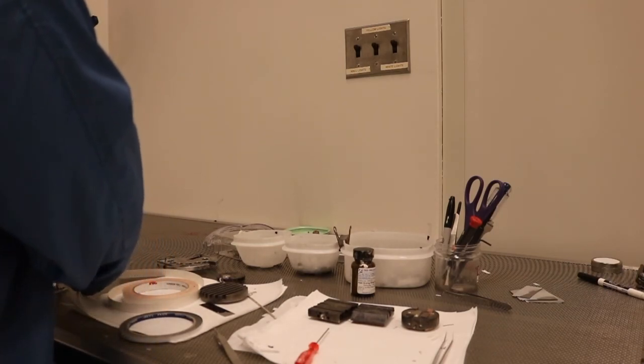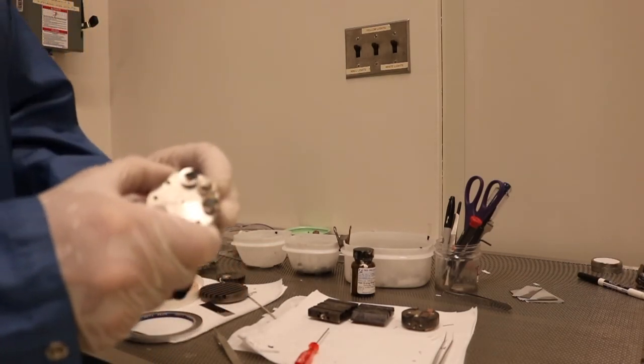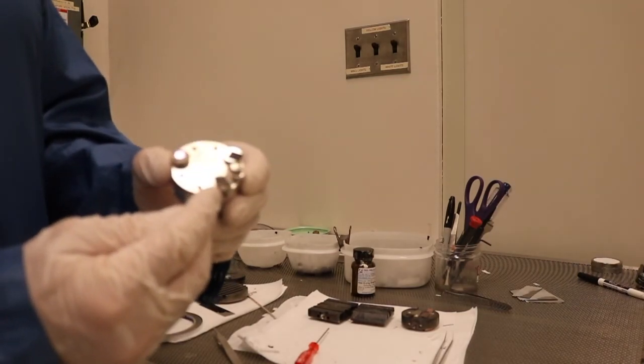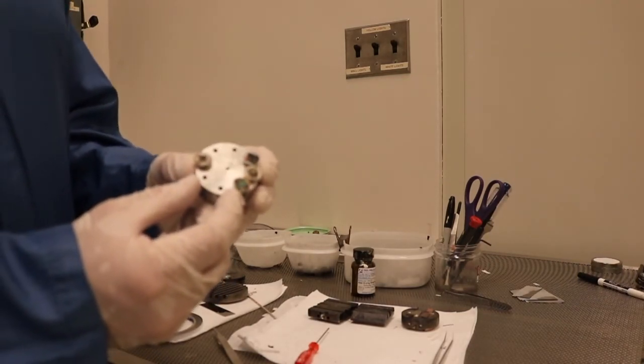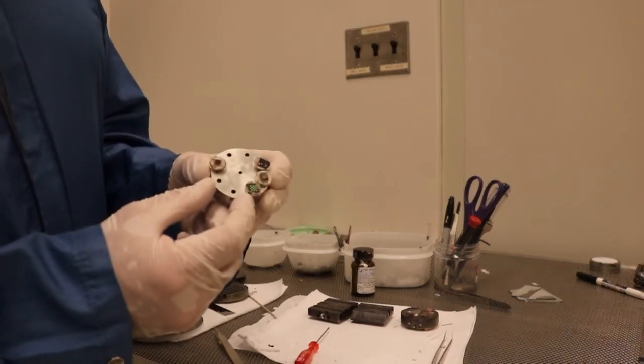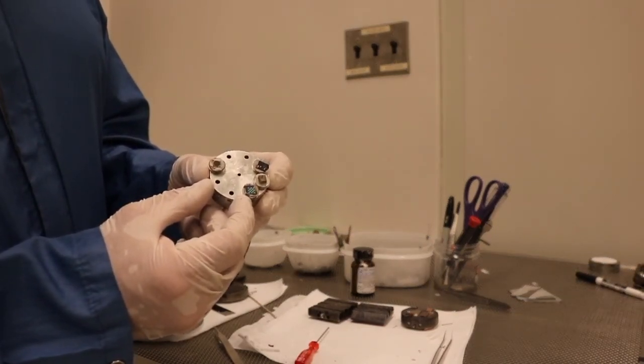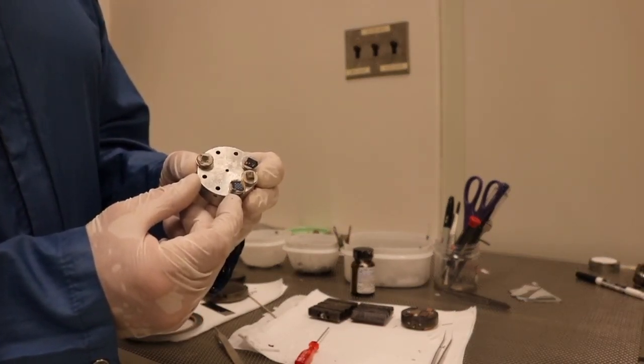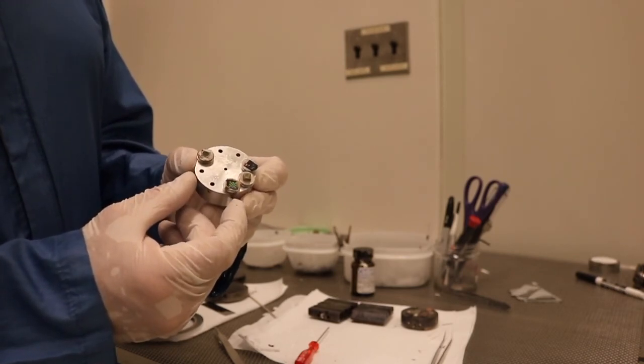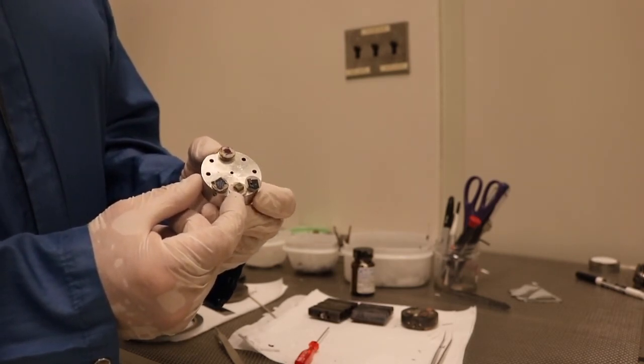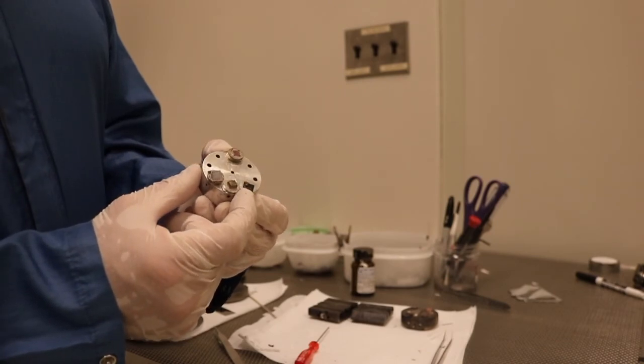I have a set of samples that I've already prepared for this. We have a few standards here. A Chessy grid standard, which is utilized for doing calibrations. It's also very easy to focus and stigmate on since it is silicon and gold. We have a gold resolution standard, and then we have another sample that will test how well you can focus through a range of depths of field. Okay, so we'll go back from there.